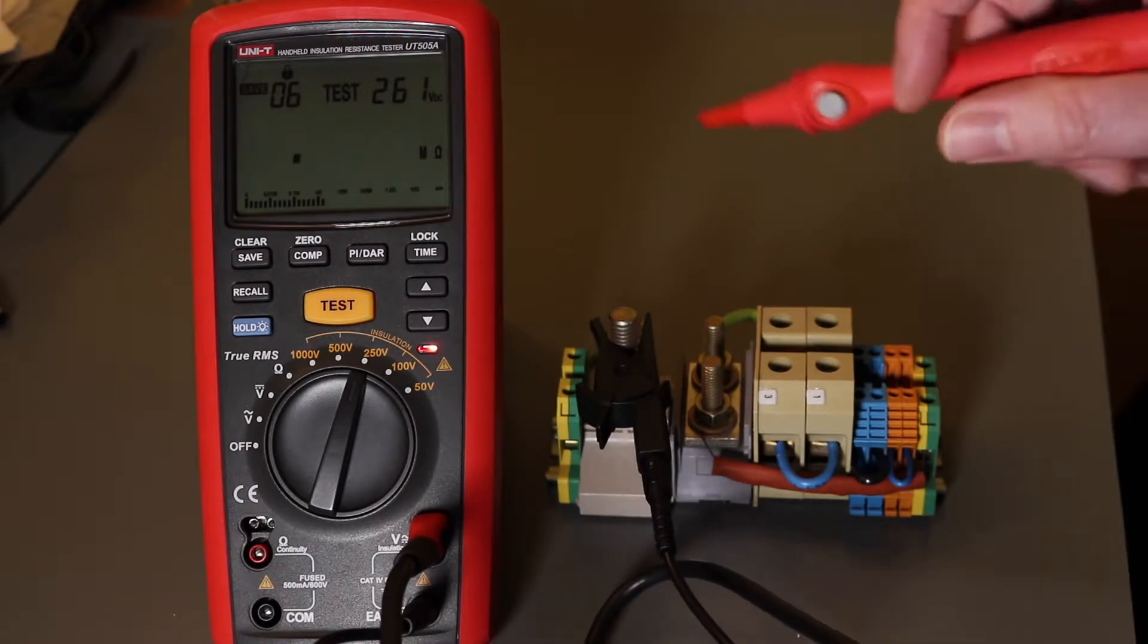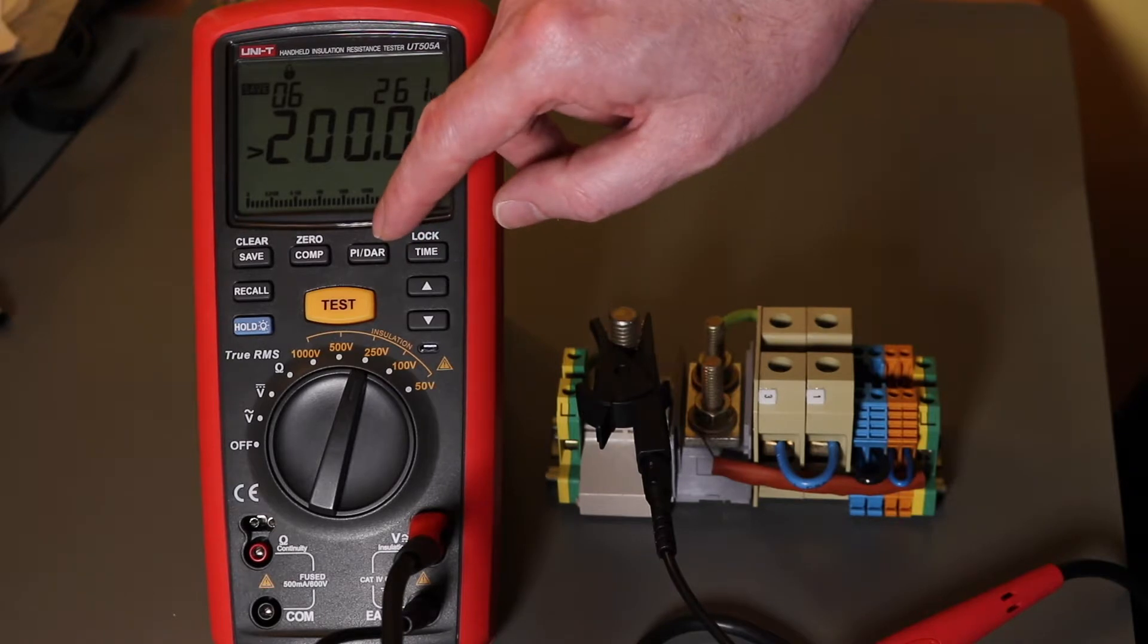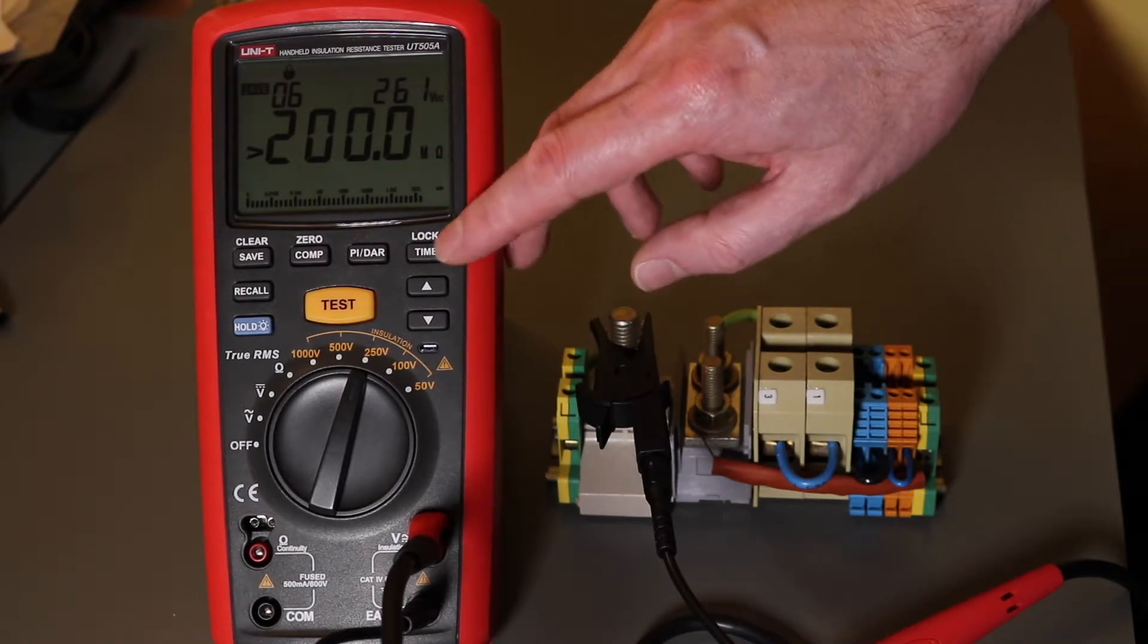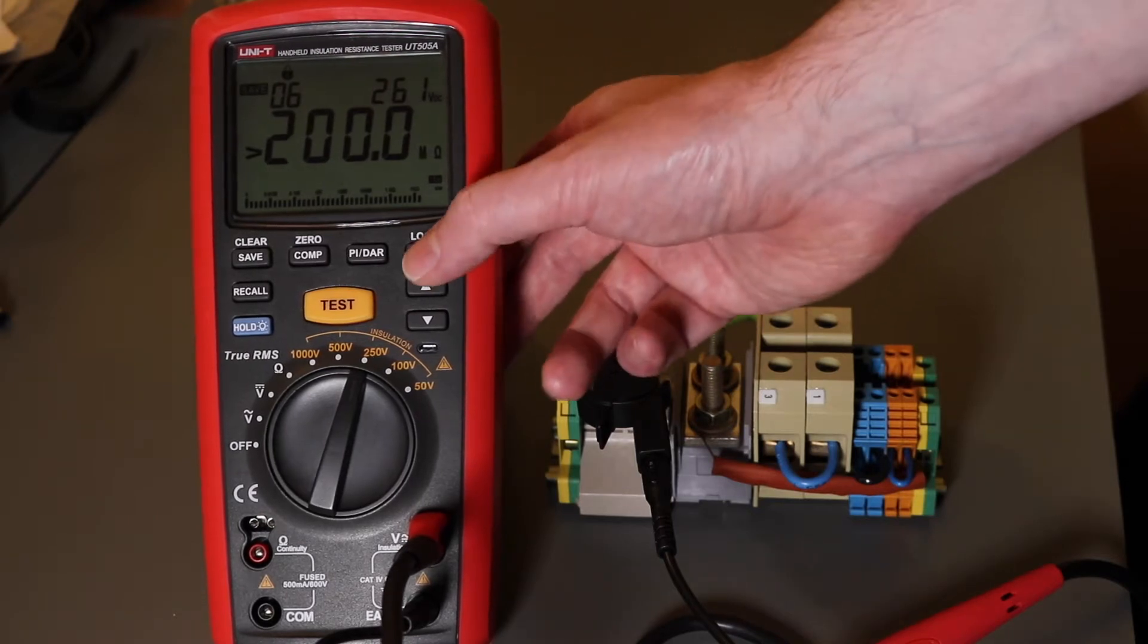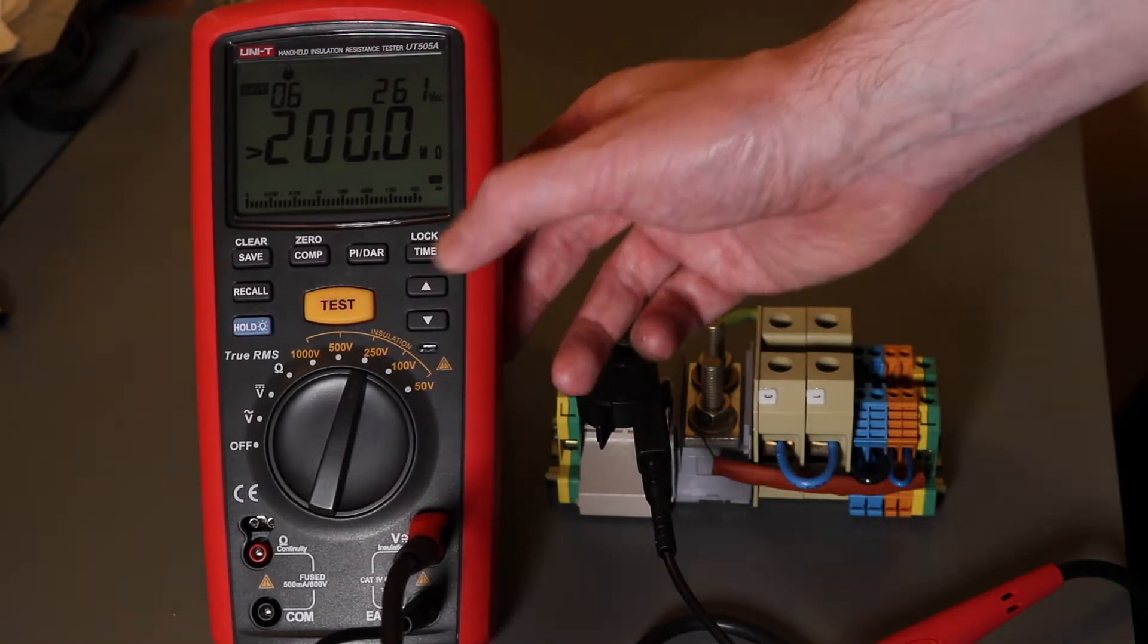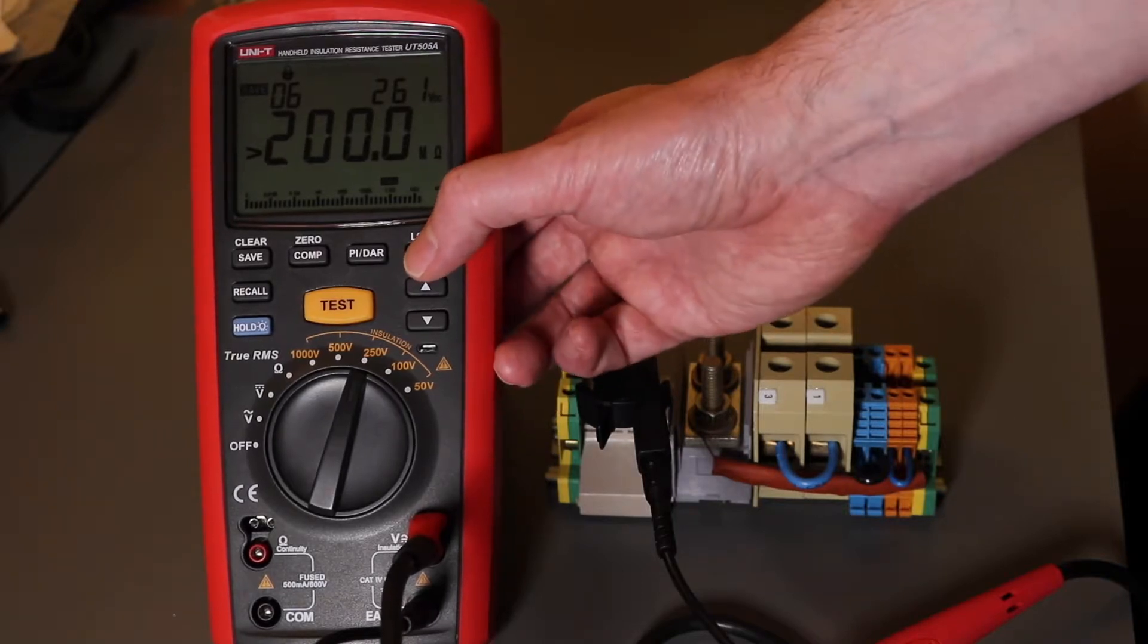I let go and you see the beeping goes. Okay so you have a time function and a PI and DAR function on this instrument. You press the time function and you'll see here it goes through various ranges. A single 15 second, 30 second or a 1 minute test.